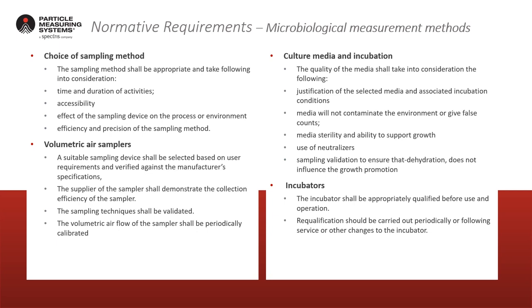The choice of sampling method should be appropriate. There is discussion around volumetric air samplers as suitable sampling devices selected based upon user requirements. The supplier of the sampler shall demonstrate the collection efficiencies. Sampling techniques shall be validated and the volumetric airflow of the sampler will be periodically calibrated. There is also discussion around the choice of culture media and incubation to ensure the right one is used in the right application, and then incubation of the sample prior to results.